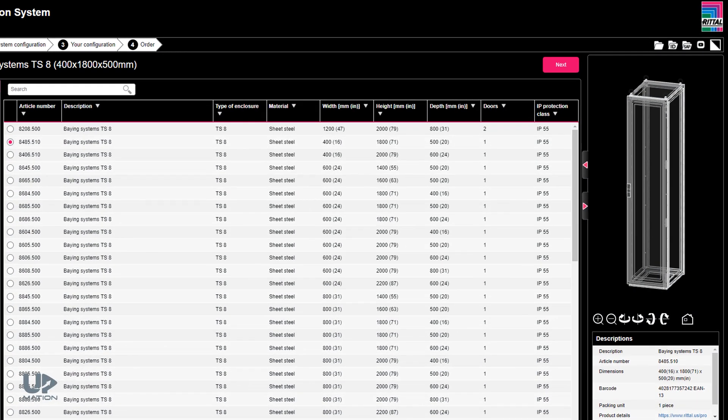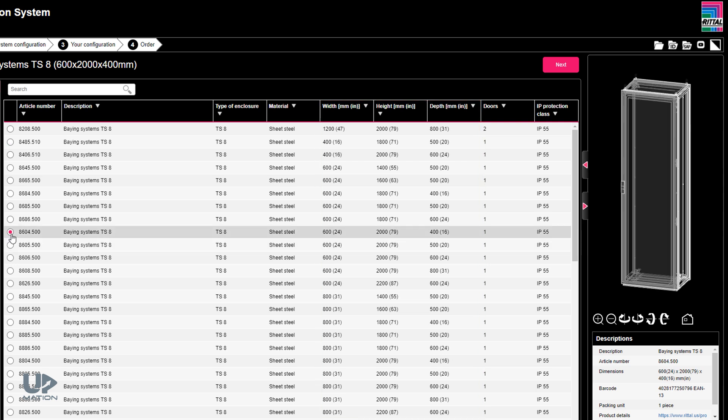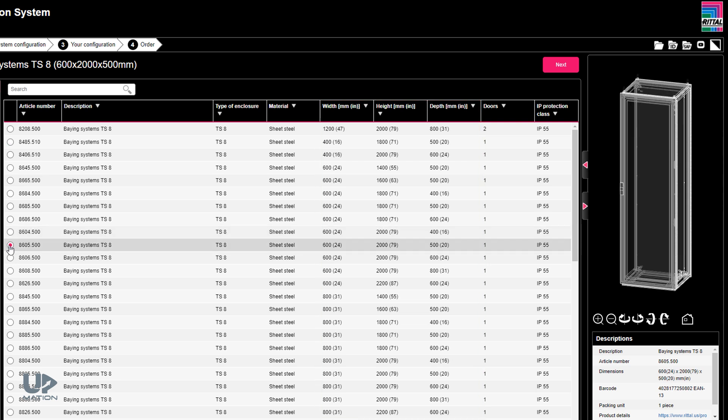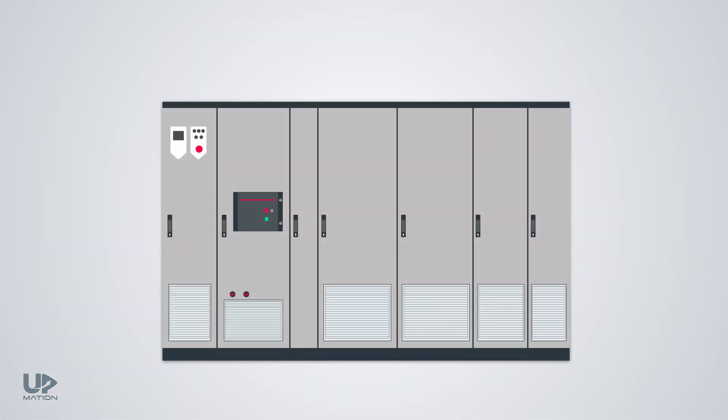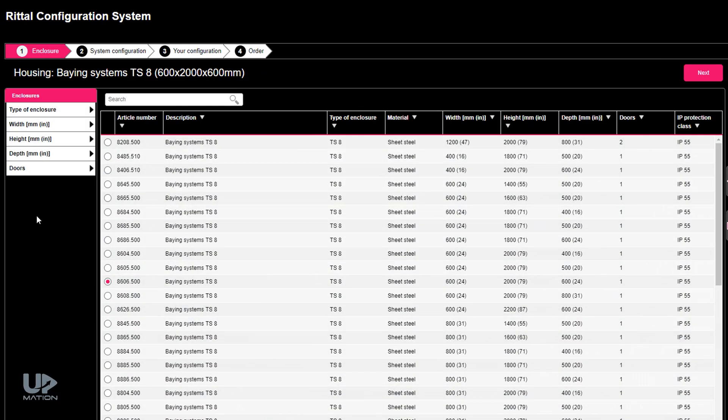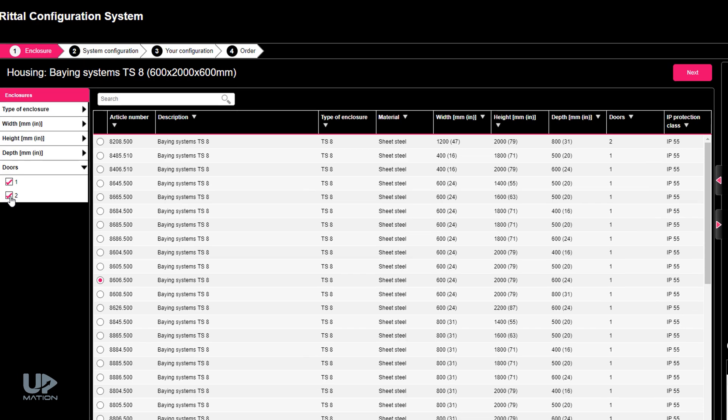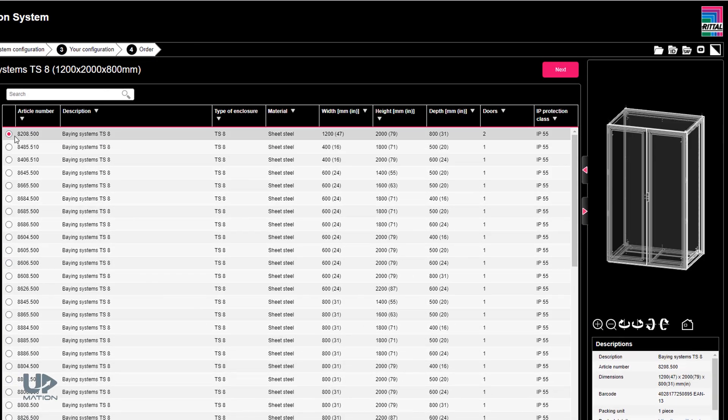Generally, there are standard dimensions for the industrial panel enclosures that we can choose among when we are designing our electrical panel. However, you might see some custom size enclosures in particular applications, such as these freestanding VFD or variable frequency drive panels. We can also choose one door or two door panels depending on the width of the panel and our desire.